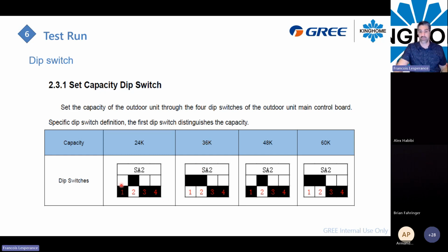Dip switch number 1, if you are looking right here: if you want to make it a 2-ton, you will have to put dip switch number 1 to the off position. Remember in the picture, the off position will be downstream and the on position will be right here. So dip switch number 1 is for the capacity. Looking at the first cabinet, the difference between a 2-ton and a 3-ton is dip switch number 1. Same thing with the other cabinet: if I want to make the 5-ton a 4-ton unit, I just flip off my first dip switch, and that's it. I will have a 4-ton unit capacity.